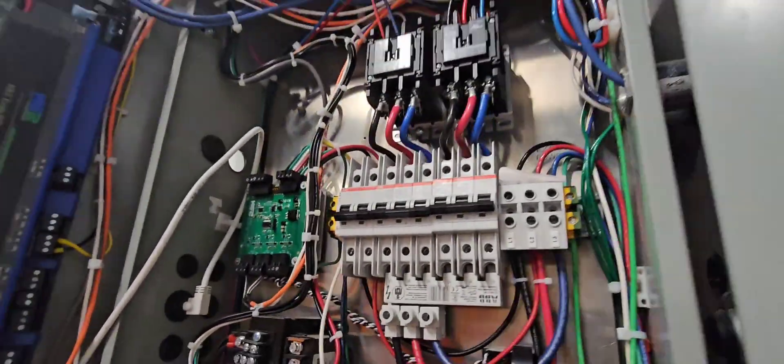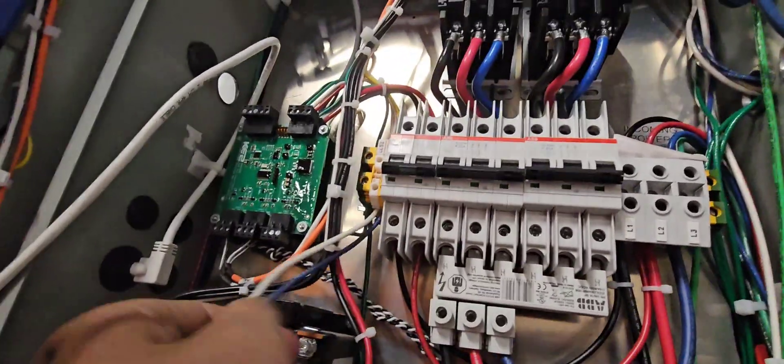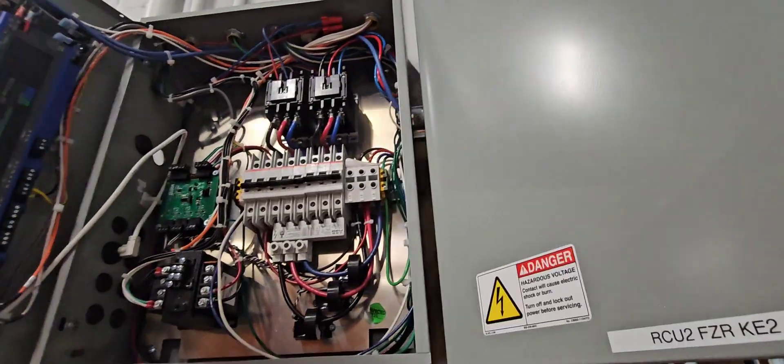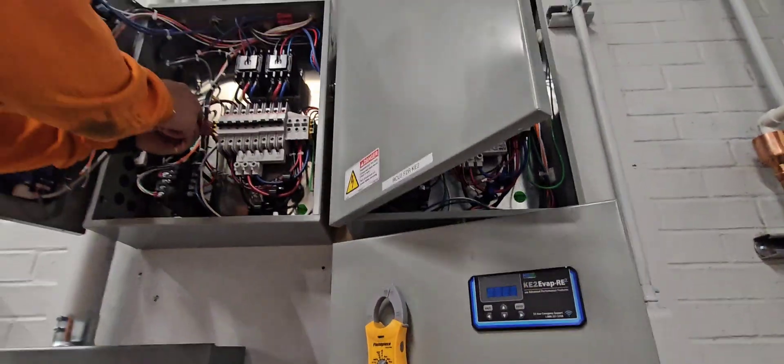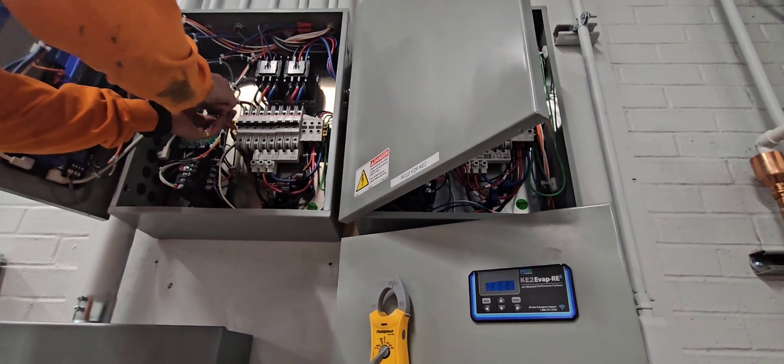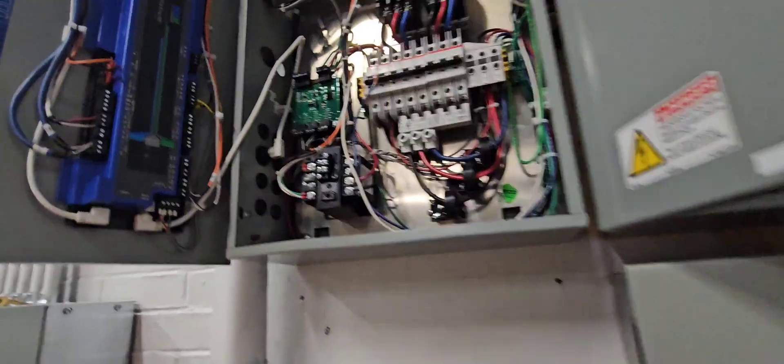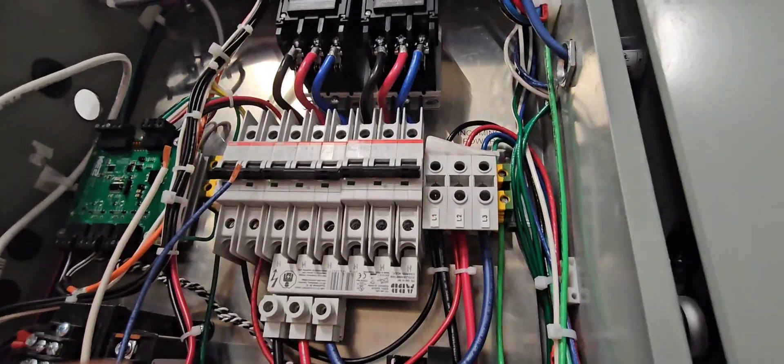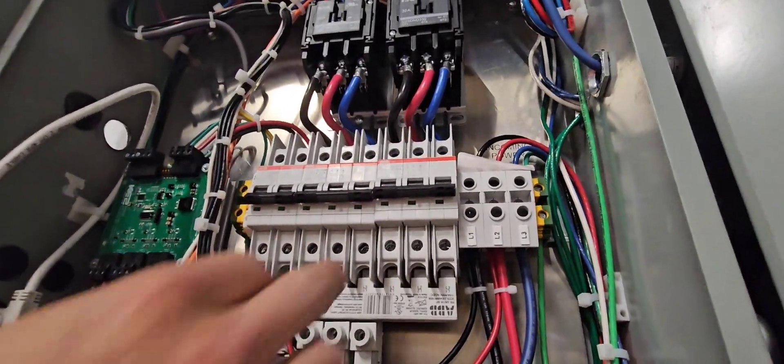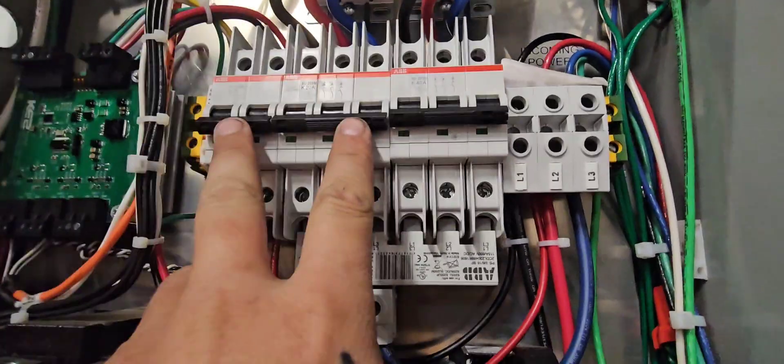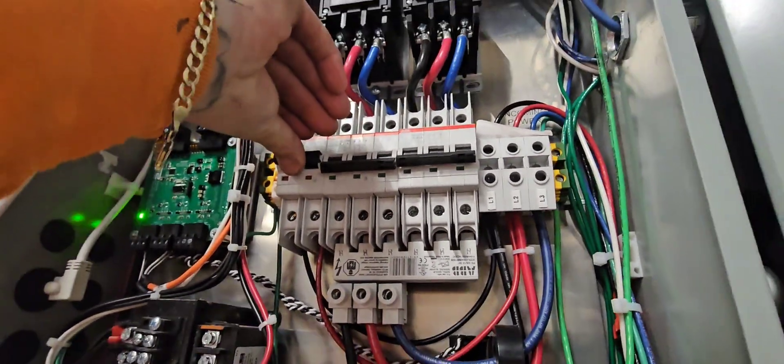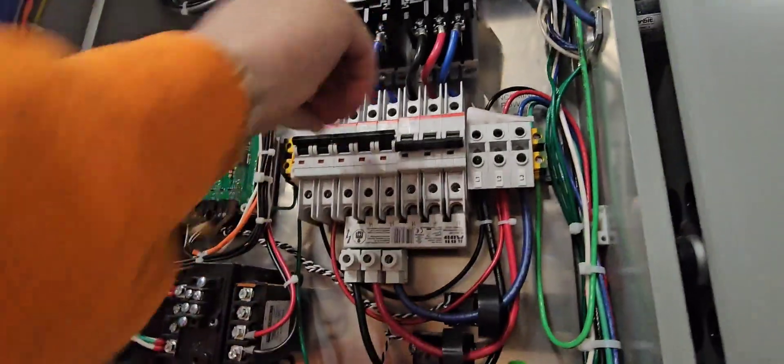We got those taps switched and now what we're doing is just taking these wires off of our solenoids so that way when we get power to that board the solenoids don't kick on while we're trying to charge. We're going to charge this thing pump down and then once we got the charge dialed in then we'll open it up. I've got those disconnected now. We're just going to start flipping these breakers on. All of them. So evap fan, these two for our evap fan and our control, the small ones the control which that stuff should all start lighting up, and then that one's just for our fans.